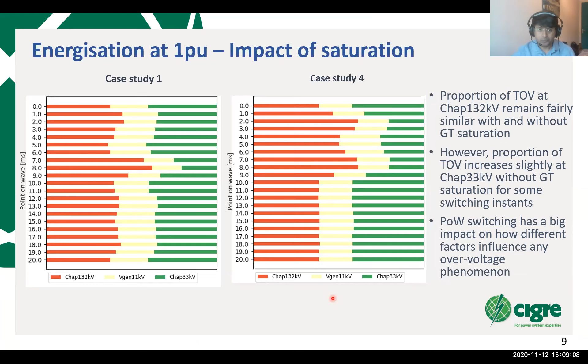Looking again from the point of view of the worst and the best case scenario, we see that in case of Chapel Cross 132 kV, the maximum and the minimum overvoltages have reduced when we do not have any transformer saturation considered. But in case of 33 kV Chapel Cross voltage, the overvoltage seems to have increased in this case. This is also something we can see from the instantaneous response.